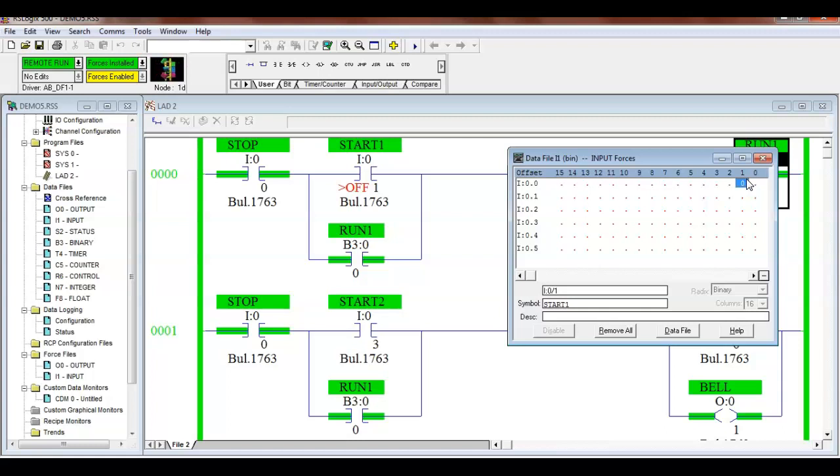So all the material was fed up to the top on a conveyor belt. And they would open a hopper door, drop it down, and then open another hopper door and drop it in. And they were having problems with one of the hopper doors. So they locked it out. They did everything they needed to do. And he wanted him to go down there and force the contact, and the guy went down there and forced the contact on the other hopper door, which they didn't do one.